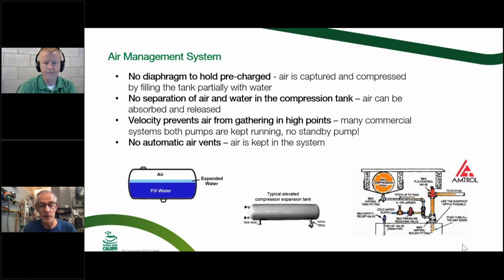For our Discal air separators, we actually make a little fitting that you can put a tube on, and you could take the discharge of that air vent up there. So any air vent that comes out through the disc valve would go up into the tank. So if you do want to put an air elimination device on that type of system, just get the air back up into the tank, just don't vent it.